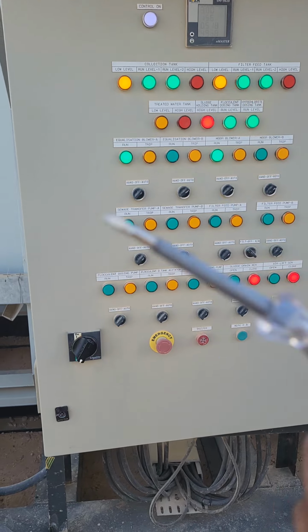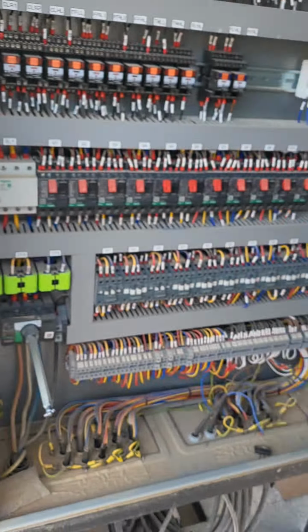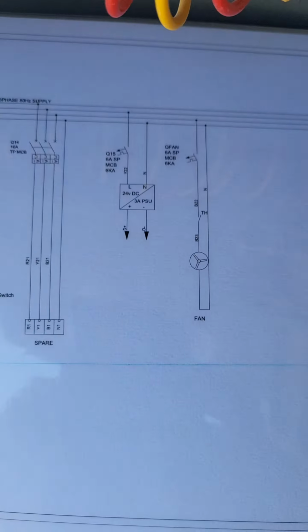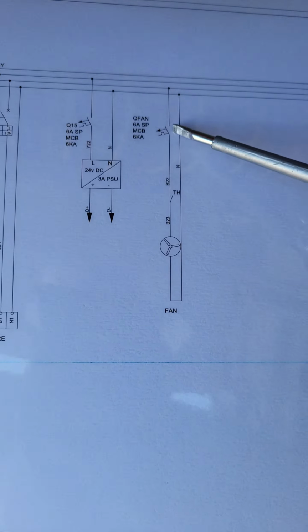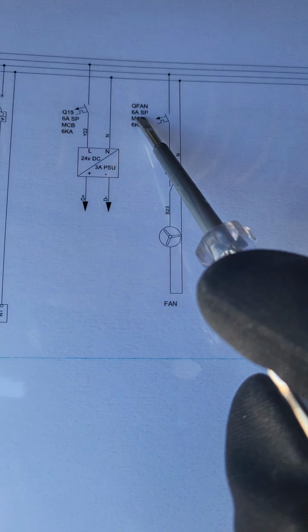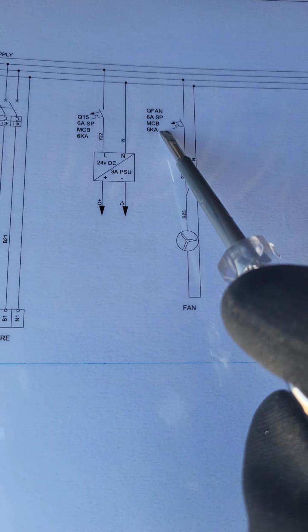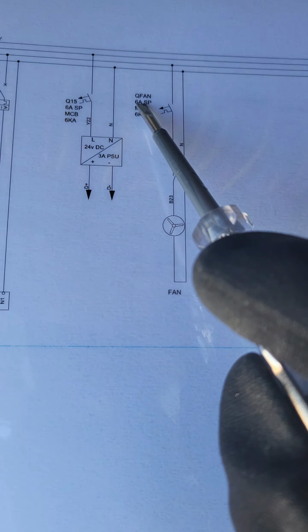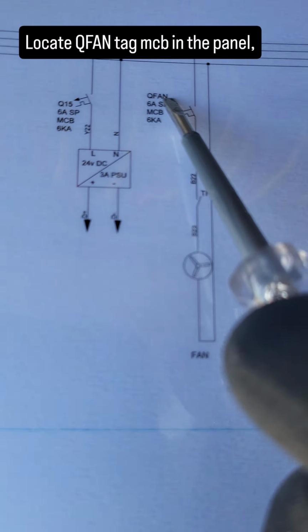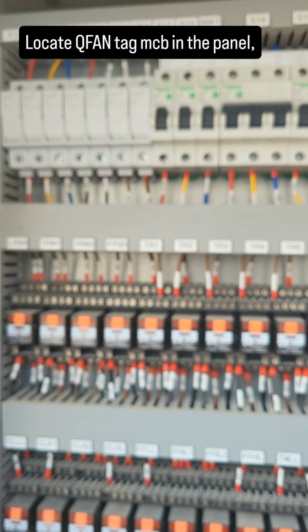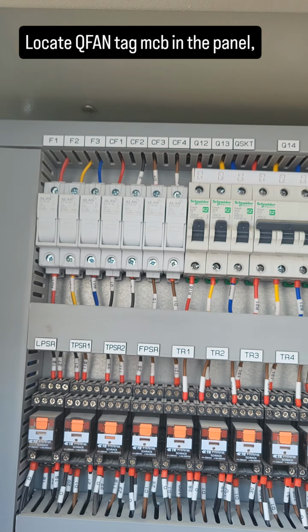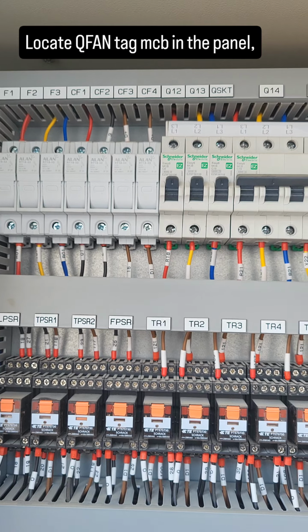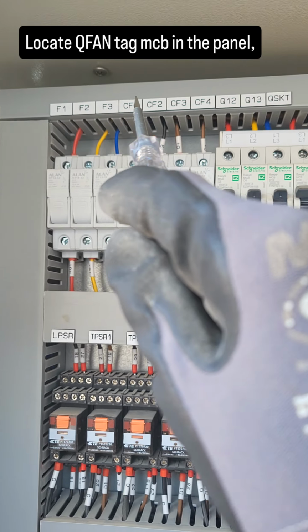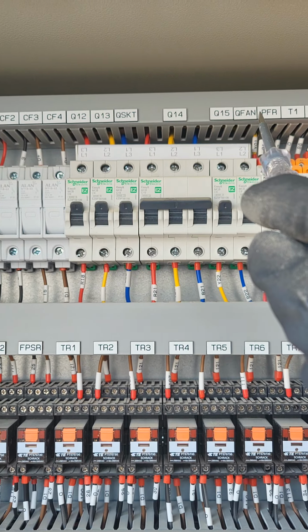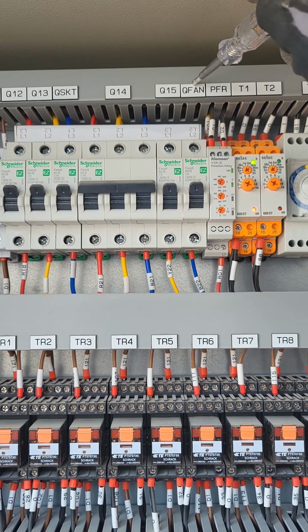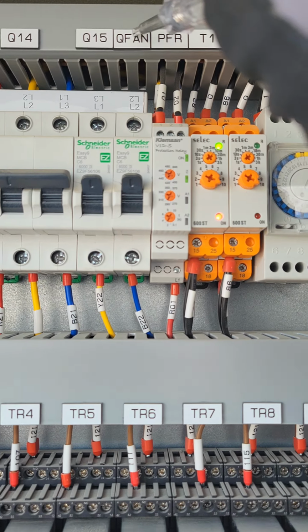Now here is the panel. Now we will open the panel. So here is the drawing. One line from the phase comes directly to the MCB named Q fan, which is 6 amps and single pole. So let's check the MCB in the panel. Now see the naming on the panel: F1, F2, F3. Now we have to search for Q fan, and this is the Q fan here, Q fan MCB, single pole MCB.